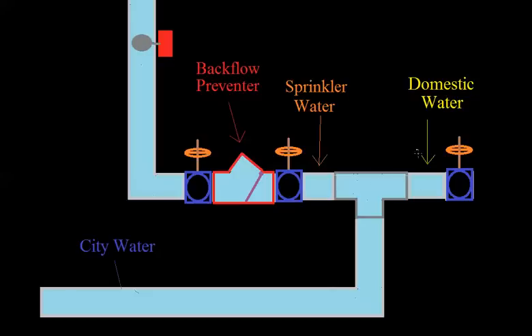And the domestic water's over here. That's the water you drink and shower with and all that. And then there's what's called a backflow preventer, which is basically a check valve. So this purple gate here is hinged, so it would allow water to flow this way. The gate would just lift up, but it won't allow it to flow back, hence the name backflow preventer.